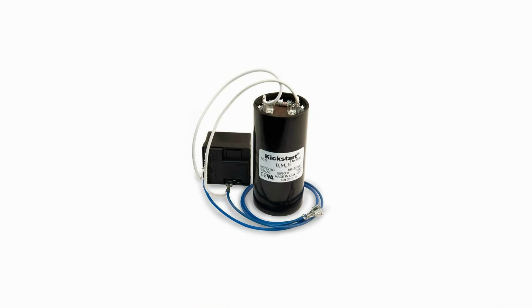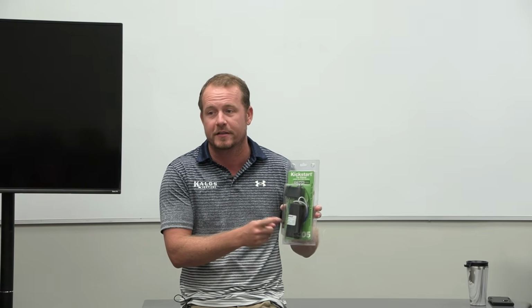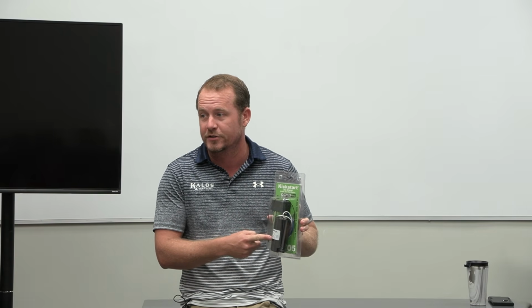This is an aftermarket hard start kit. Okay. And we stock these. So, contrary to popular belief, I am not against hard start kits, in situations where a compressor is locked and everything else is as it should be. But do we go to this first? No, what do we check first? Check a capacitor. What else do you check? Incoming voltage, that'd be a good one. What else do we check?